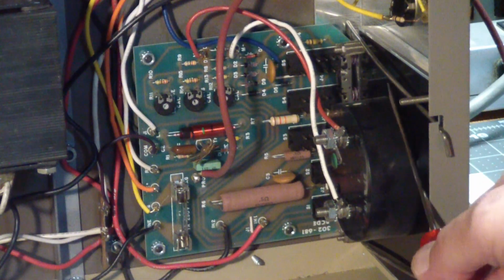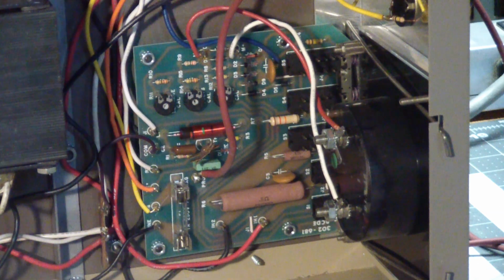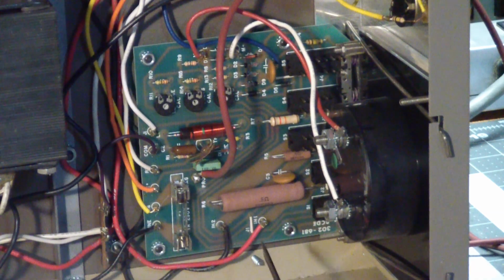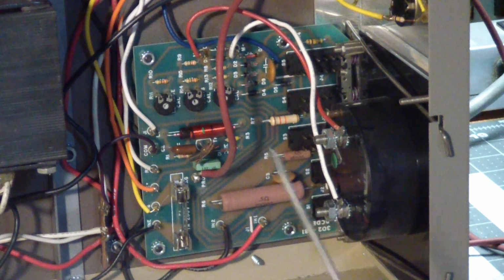So what do we have here? This is, of course, the meter, and here's the circuitry that drives it. Whatever the problem was - and I did verify it - it was showing, well, it wasn't showing half the actual voltage. It was probably showing about a third of the actual output voltage. So yes, we definitely had a problem in here.